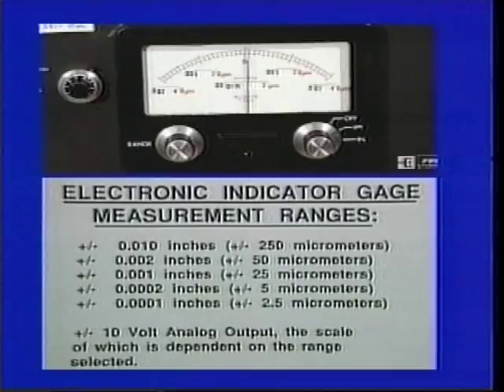The gauge console offers 5 measurement ranges, as well as a plus or minus 10 volt analog signal. The available ranges are plus or minus 0.01 inches, plus or minus 0.002 inches, plus or minus 0.001 inches, plus or minus 0.0002 inches, and plus or minus 0.0001 inches. The voltage to displacement conversion factor for the analog signal depends on the range selected. A choice of metric or English units is also offered.